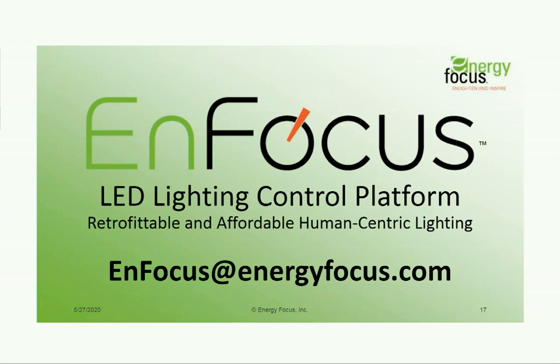Okay. Thank you. Let me move on quickly. One of the things EnergyFocus is known for is our flicker-free products. You mentioned in the beginning low flicker. The question is: is the flicker level low enough to be ignored, or should I expect some noticeable flicker? If I can, please, John. Yeah, let me take that. I think I know where he's coming from. These triac-based control systems that work with LEDs often flicker, especially at low levels. This has to do with the way the triac controls work. They were controls, of course, that were originally designed for incandescent bulbs. Since the EnFocus system doesn't use triacs, we do the control in the lamp. We shouldn't, and we don't, see flicker as a result. So that was a great question.